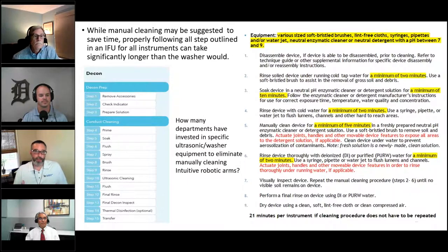The other thing is, and this goes along with the preferred approach—this is a little thing from the Intuitive IFU about some of these steps: prime, soak, flush. The reason we've got ultrasonics with pulse flow and things like that, and needing that lumen testing like Kevin talked about, is because that's integral to that piece of equipment cleaning that device properly. So we invest in this equipment for its repeatability, for its consistency, and for it to help us. You should really take a pause before you say, yeah, I'm going to skip this very helpful piece of equipment and just do it by hand. There should be a good reason for it, and you have to know you're prepared to do it if you're going to make that choice.